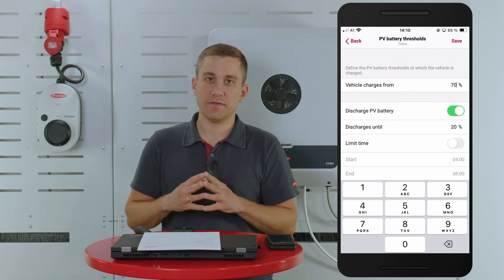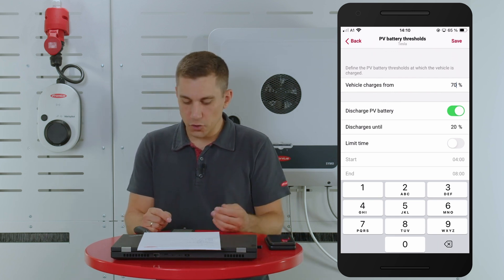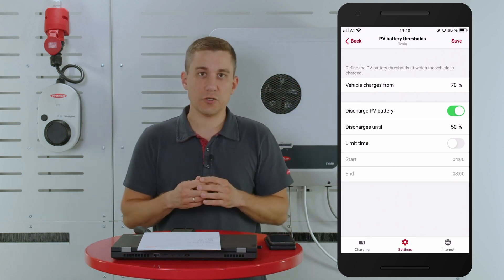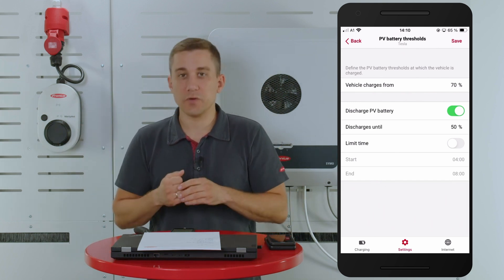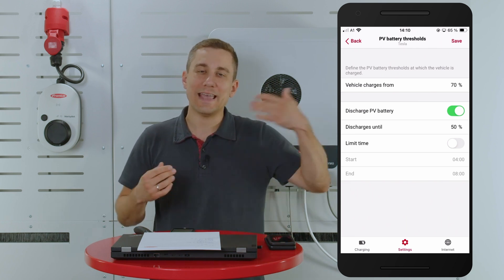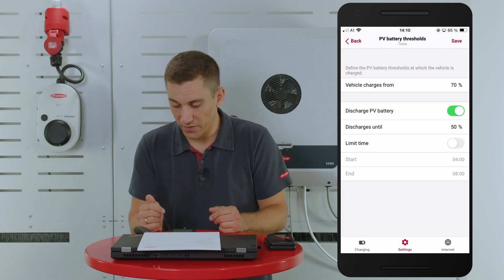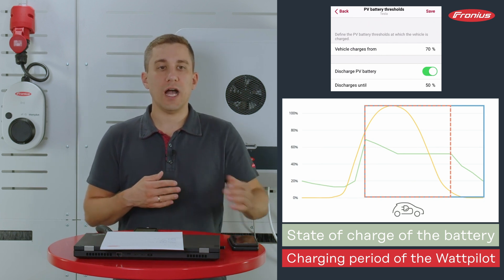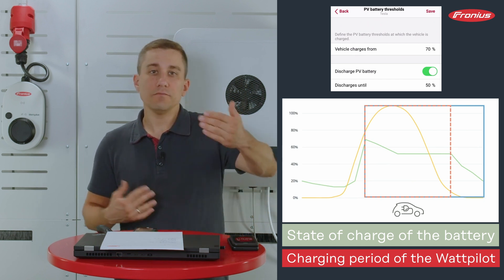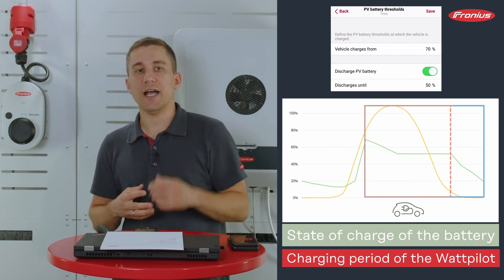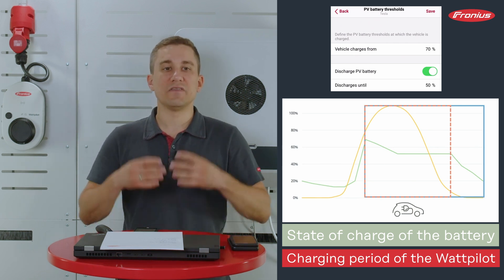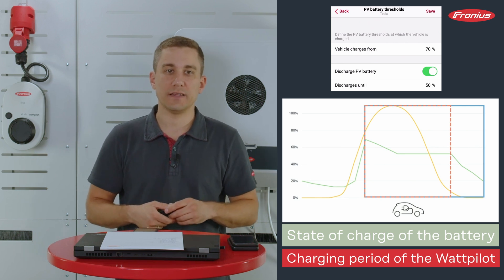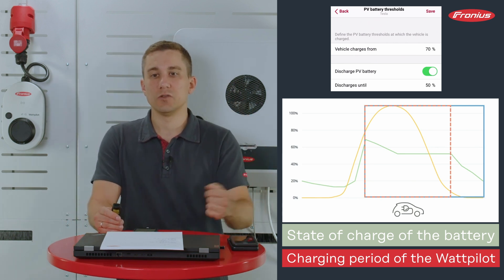The second feature is the discharge functionality of the PV battery, where you can set a discharge value. In our case, we are setting this to 50%, since you need at least 50% of your stationary battery to get through the nighttime. With 50%, you have enough energy for the nighttime loads to be supplied with PV surplus energy without drawing from the public grid. As shown in the schematic, the stationary PV battery charges to 70%, then the vehicle uses that charge down to 50%, at which point discharging stops and the 50% capacity is reserved for nighttime household loads.